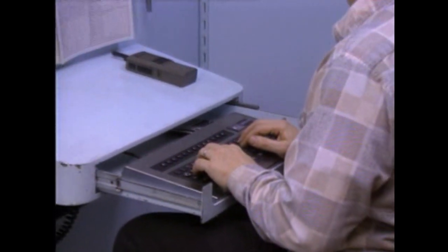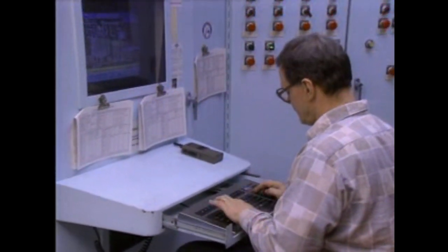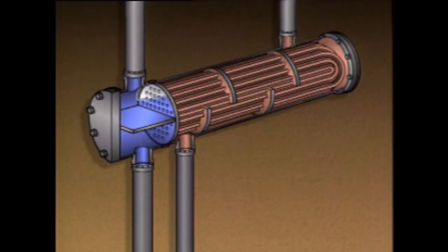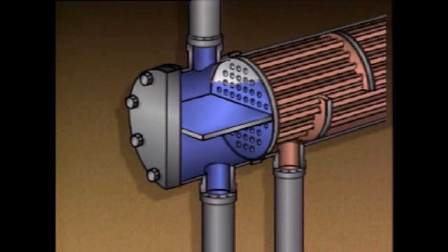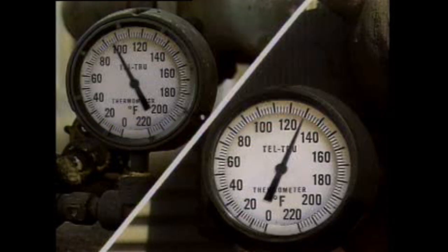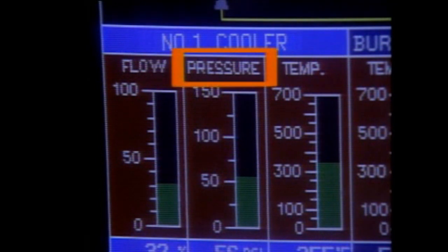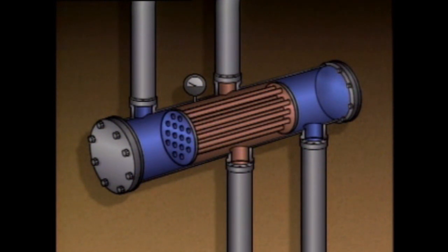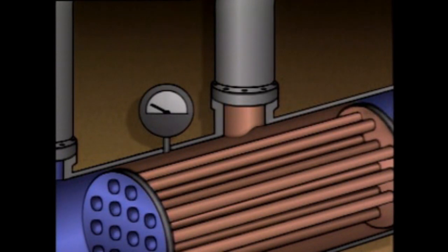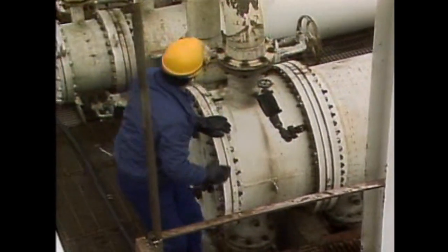No matter how air or other gases get trapped inside a heat exchanger, they can cause it to become air-bound or vapor-bound. For example, when trapped gas blocks flow to some of the tubes, the outlet temperatures of the two fluids may change because the gas is restricting flow into the tubes and reducing the available heat transfer surface area. The decrease in heat transfer surface area will cause the outlet temperature of the process fluid to increase, since less heat will be removed from the fluid. There are also situations where the pressure inside a heat exchanger may be affected — in heat exchangers used to condense process vapors, non-condensable gases can partially fill the unit, reducing heat transfer area, decreasing the amount of vapor condensed, and ultimately causing pressure inside the unit to increase.